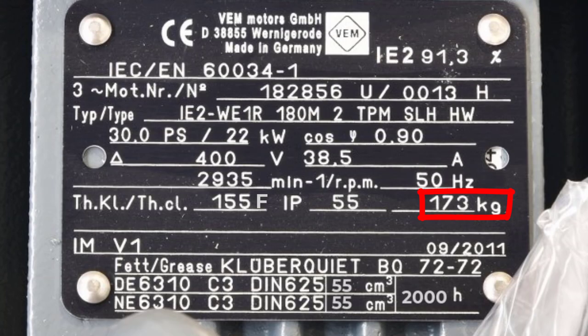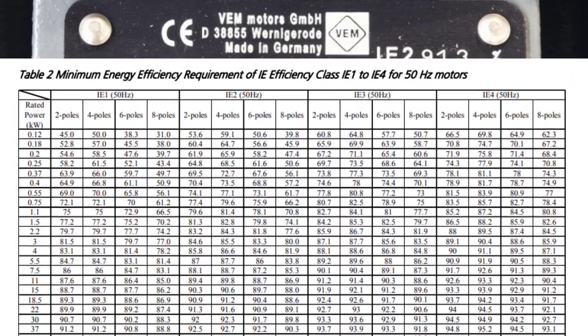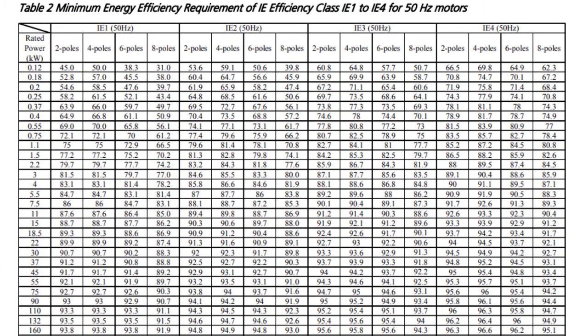Motor weight is 173 kilograms. On the top right, we have the international efficiency classes: IE1 (standard efficiency), IE2 (high efficiency), IE3 (premium efficiency), and IE4 (super premium efficiency). Using the output power and number of poles, we can look up the full load efficiency. In our case, with 22 kilowatt, 2 poles, and IE2, the efficiency equals 91.3%.